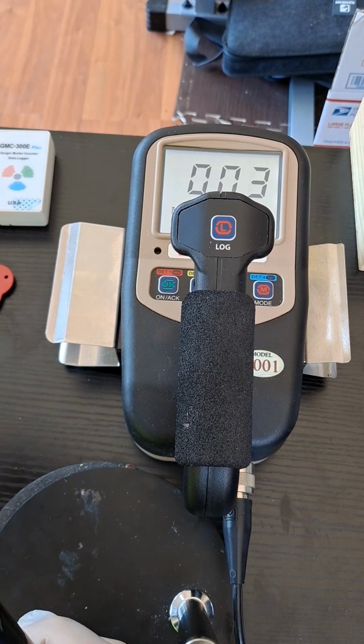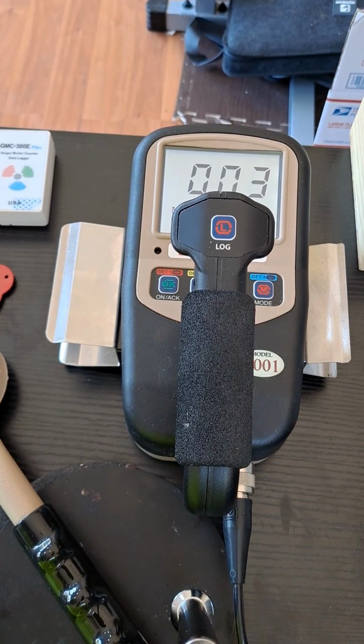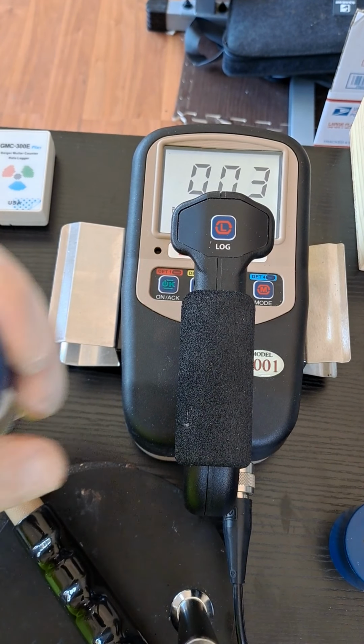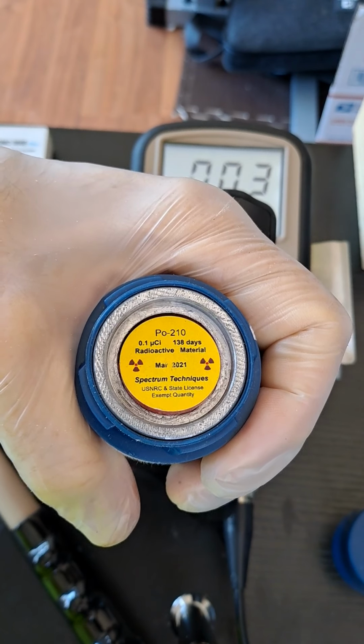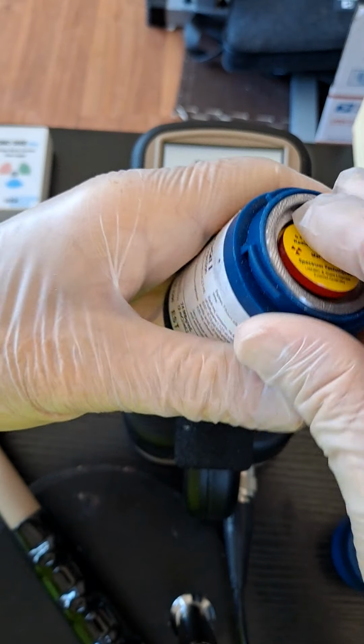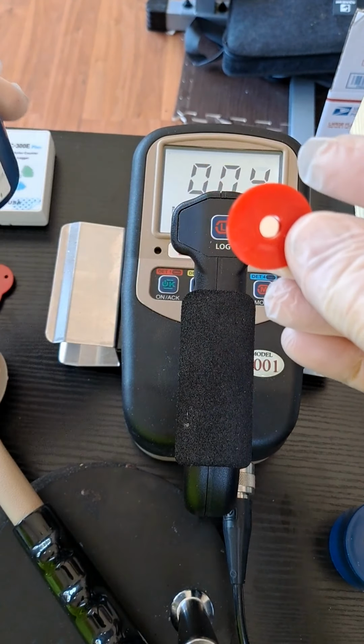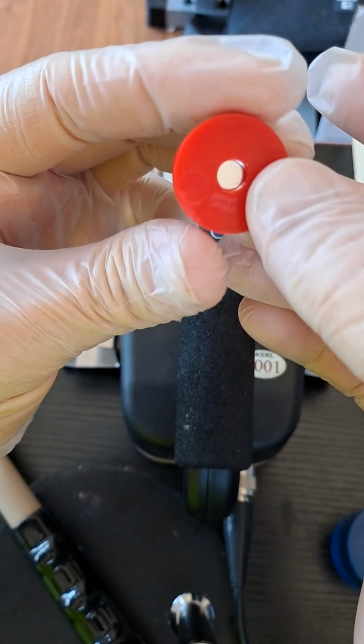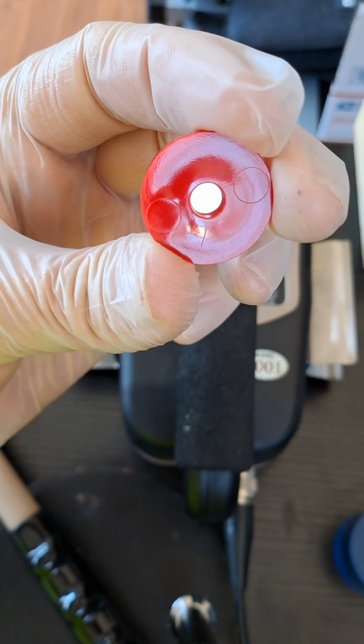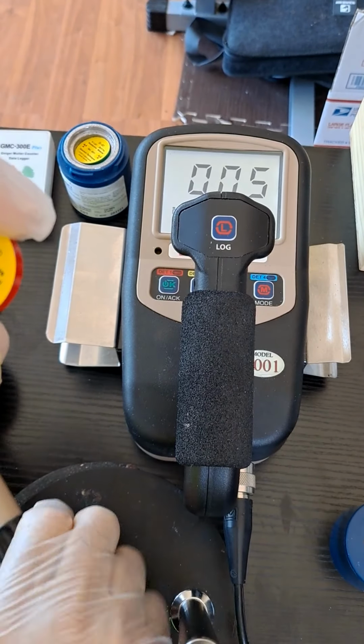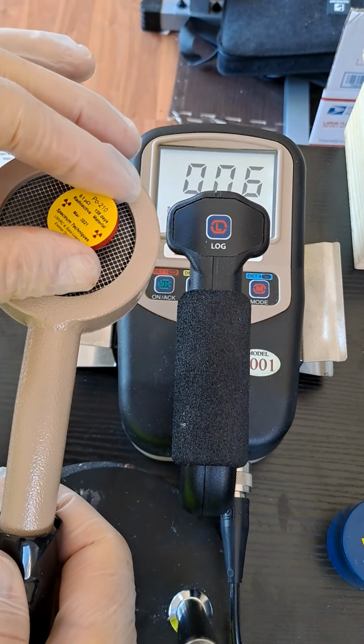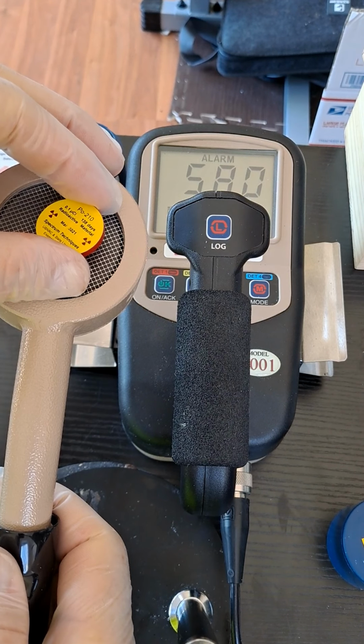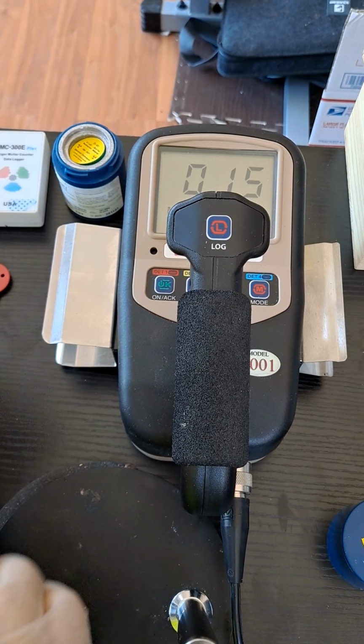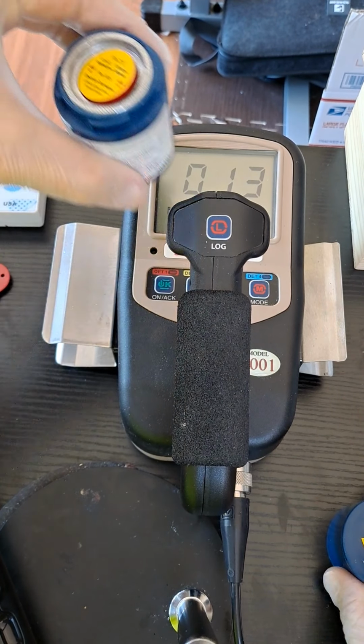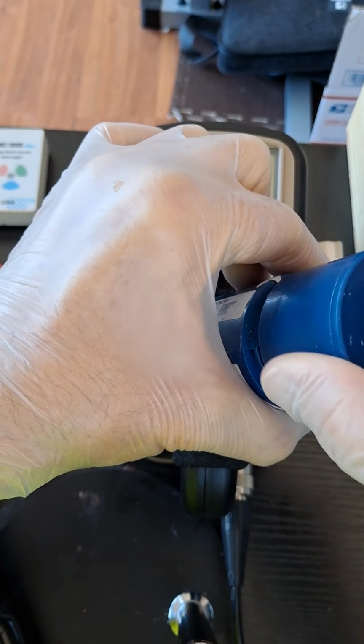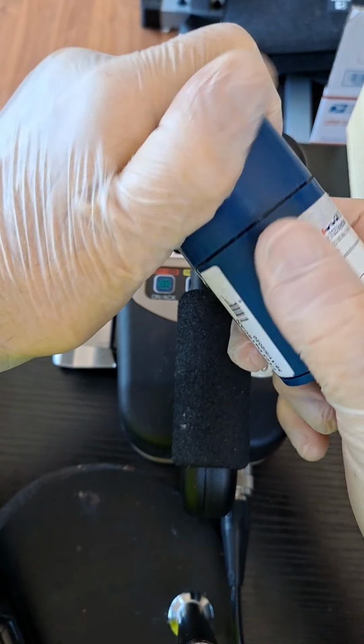And to make sure your instruments are working, you then must test them out. So I have what they're called license-exempt sources. As an example, that's polonium-210. They're in the legal amounts individuals are allowed to own. You take one out. See the little hole here? That's where the alpha comes out. Alpha is so weak, it will only go the thickness of a piece of paper. But if I put it on my pancake probe, you can hear it definitely is a good source. Before you use your instruments, you need to check to make sure they're working. Now to keep them stored, it's called a little pig. You then lock your sources away in the pig to keep their radiation levels down.